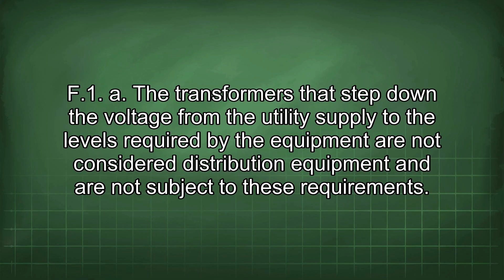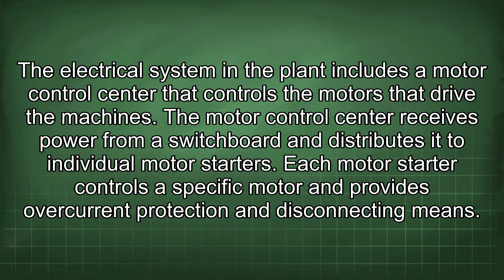Now let's consider another example, a manufacturing plant with various machines and production equipment. The electrical system in the plant includes a motor control center that controls the motors that drive the machines. The motor control center receives power from a switchboard and distributes it to individual motor starters. Each motor starter controls a specific motor and provides overcurrent protection and disconnecting means.